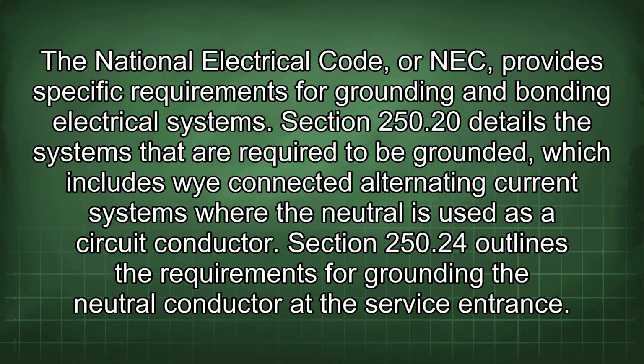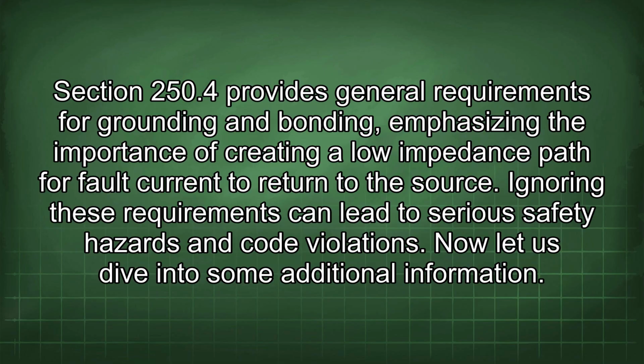The National Electrical Code, or NEC, provides specific requirements for grounding and bonding electrical systems. Section 250.20 details the systems that are required to be grounded, which includes Y-connected alternating current systems where the neutral is used as a circuit conductor. Section 250.24 outlines the requirements for grounding the neutral conductor at the service entrance. Section 250.4 provides general requirements for grounding and bonding, emphasizing the importance of creating a low impedance path for fault current to return to the source. Ignoring these requirements can lead to serious safety hazards and code violations.